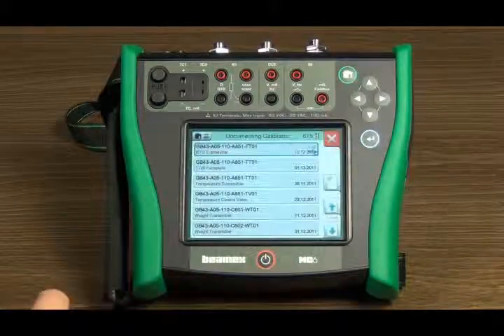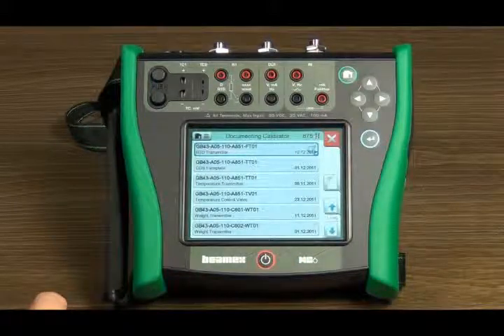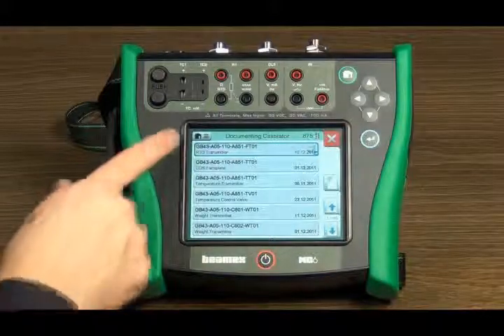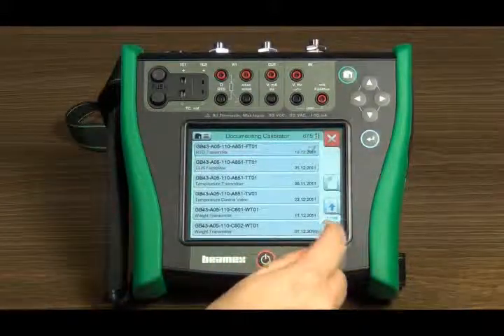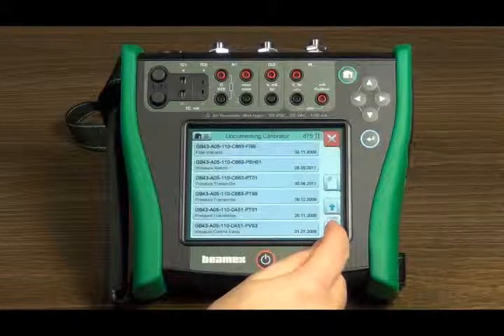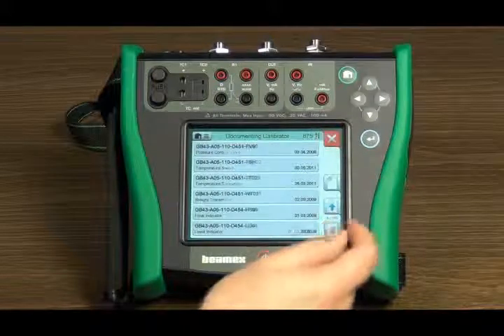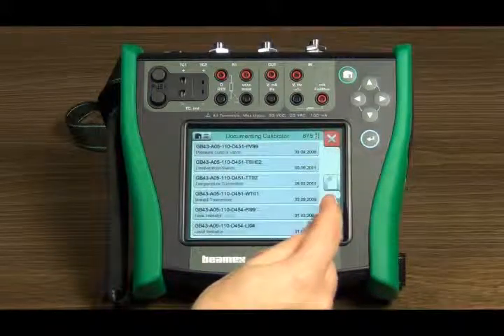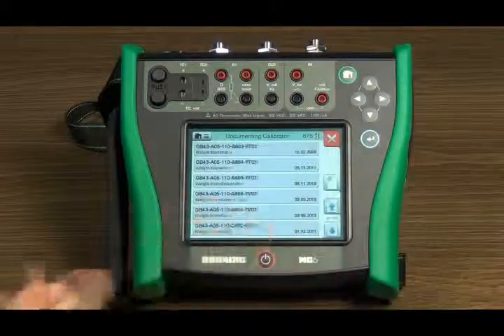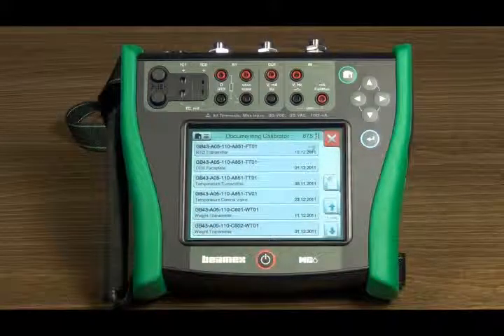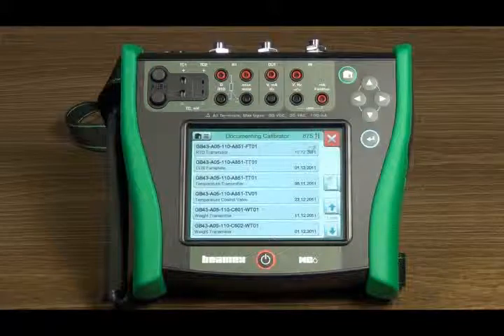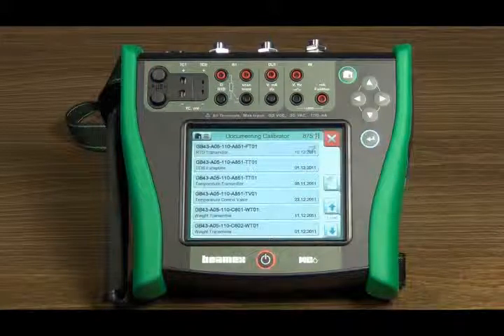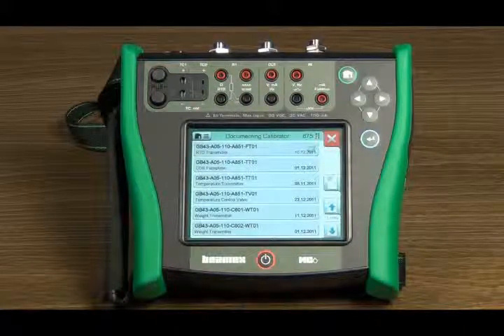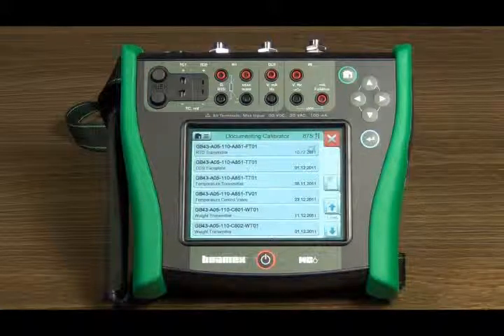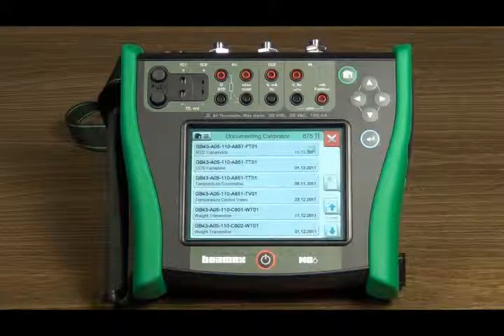You will be first shown the list of the instruments currently in the calibrator memory. These may be sent from the calibration software or created in the calibrator. An unlimited number of instruments and calibration results can be stored in the memory. You can also use the plant structure, which contains the instruments in relevant folders. If you send instruments from the Beamex CMX calibration management software, the plant structure is included automatically.